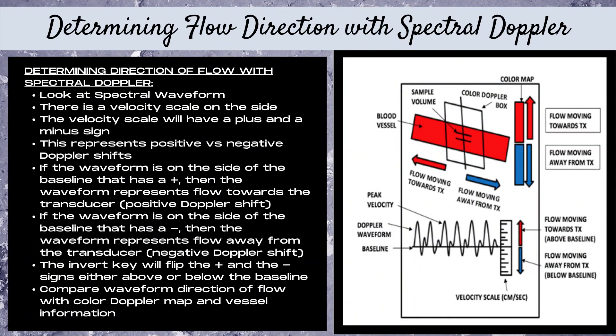Finally, how to determine flow direction with spectral Doppler. Look at the velocity scale on the side of the spectral waveform — it has a plus and a minus sign. If the waveform is on the side of the baseline with a plus, it represents flow towards the transducer (positive Doppler shift). If the waveform is on the side with a minus, it represents flow away from the transducer (negative Doppler shift). The invert key can flip the positive and negative signs, so compare your waveform with your color Doppler map and vessel information to ensure everything is consistent.